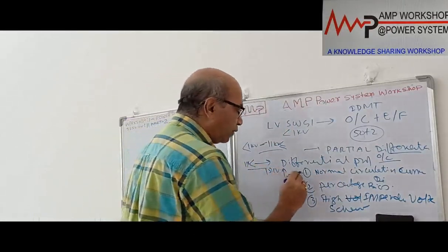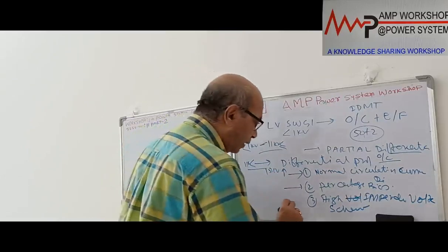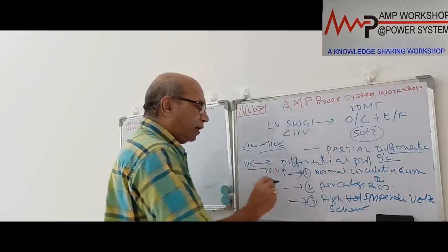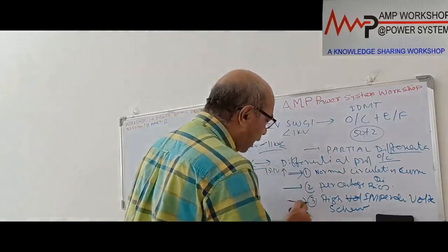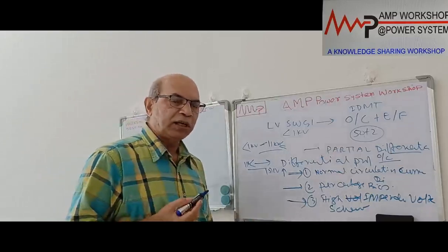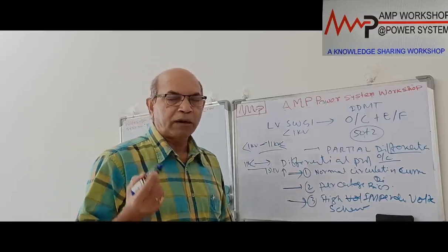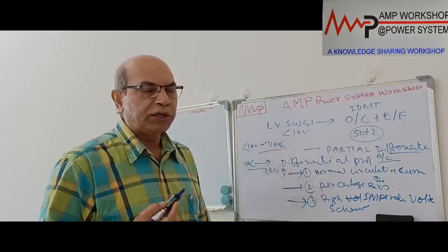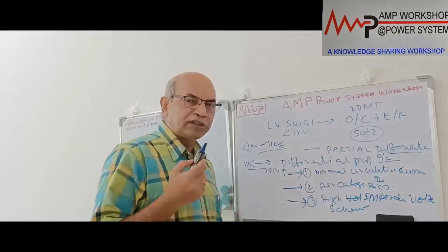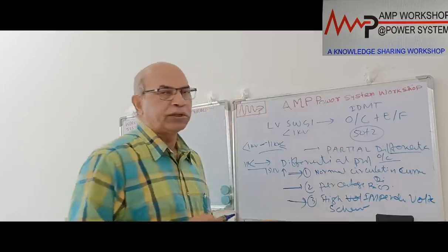This is a very low cost option, this is slightly more costly, and this is the highest cost option. This one is not very much secured, this is medium secured, and this is a highly secured option, which is expensive. So for all the most critical switchboards above 15 kV, which have a huge number of incoming or outgoing feeders, and for high voltage switchgear of 66 kV and onward, we normally go with the high impedance voltage scheme.